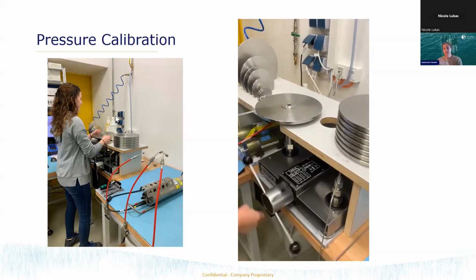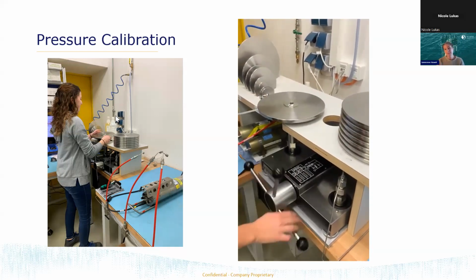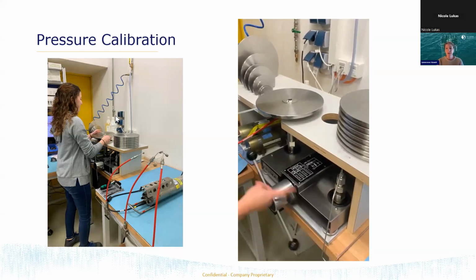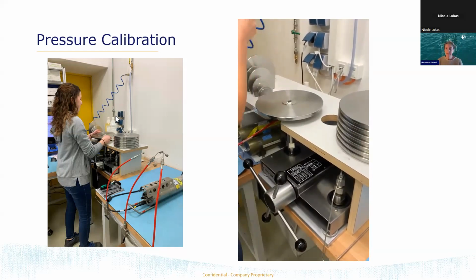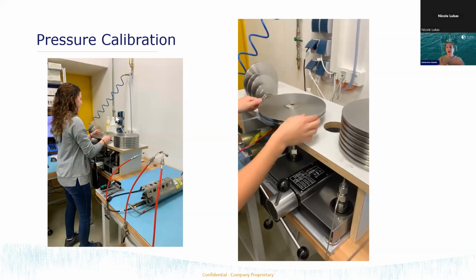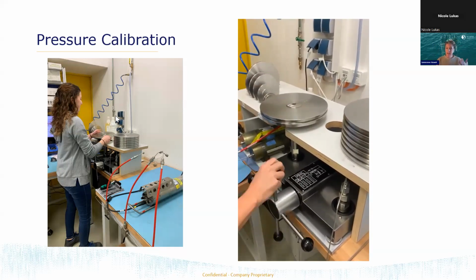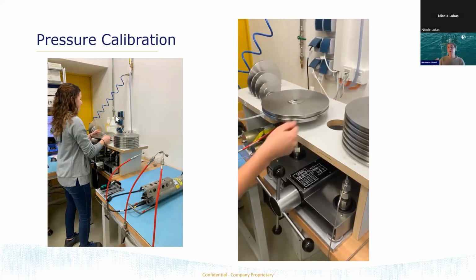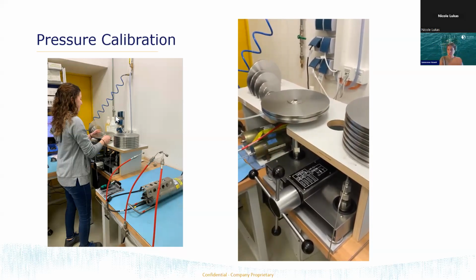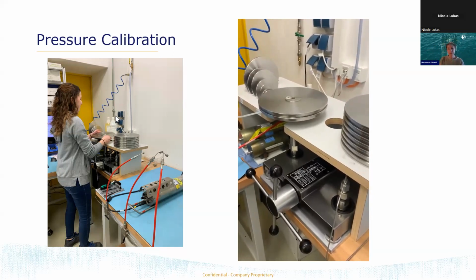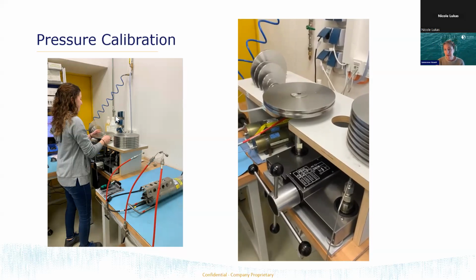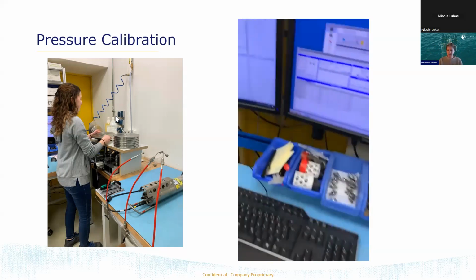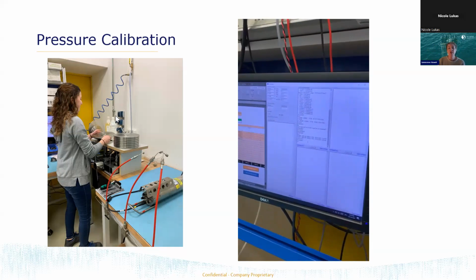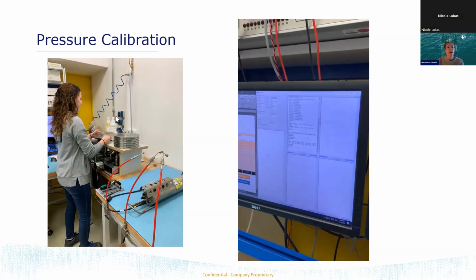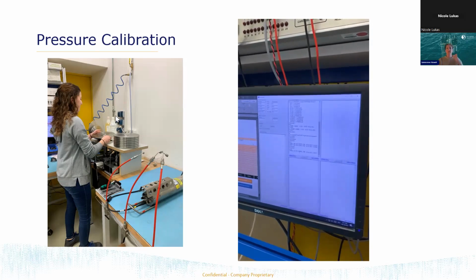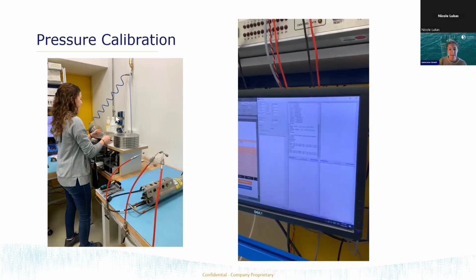And then we have a couple of different systems for creating pressure. The one that we're demonstrating here is a dead weight tester. So we're actually physically adding weights to achieve a specific pressure. And then we compare what the digiquartz reference is telling us that pressure is to what your instrument is reading. And we'll take a number of different points along the entire scale that's appropriate for that specific pressure sensor, and then generate correction coefficients, so that when you get your instrument back, the pressure is reading exactly as it should.